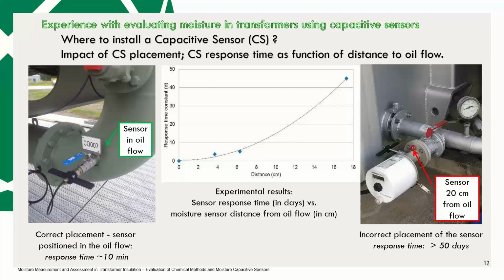And on the right side, you can see an installation in a pipe, which is actually far away from the oil flow. In such a case, you will have a very, very long time, if at all, to get a really reliable result. And the graph here is also showing the dependence of the response time on the distance of installation. So it is not enough to have a capacitive sensor somewhere. It must be in the right place.